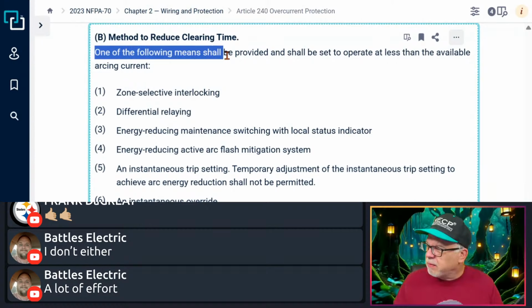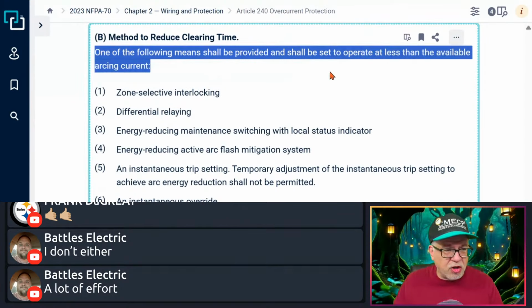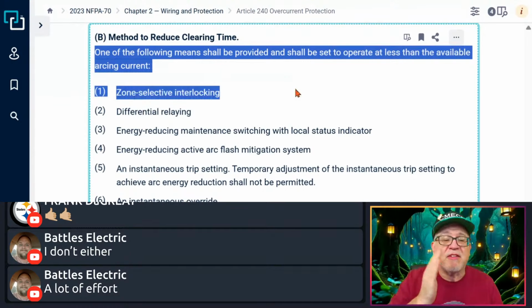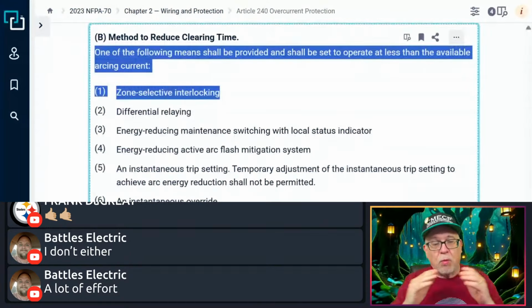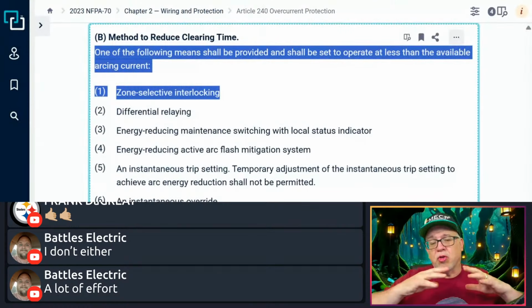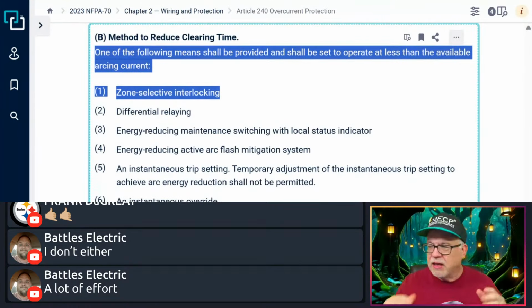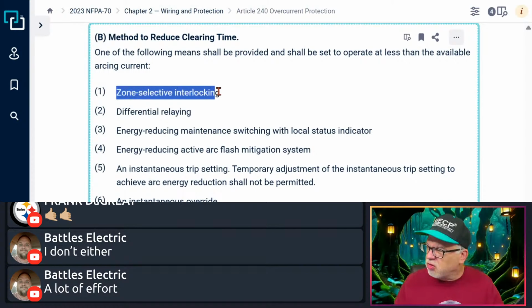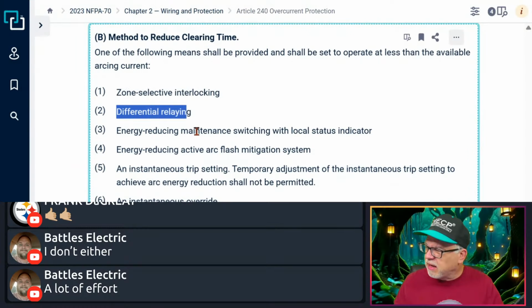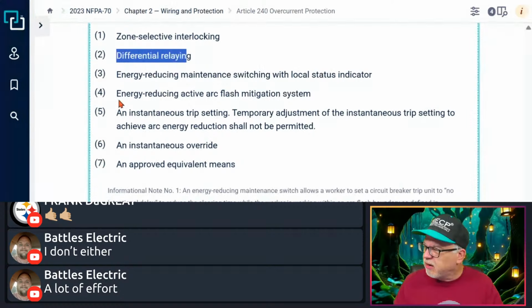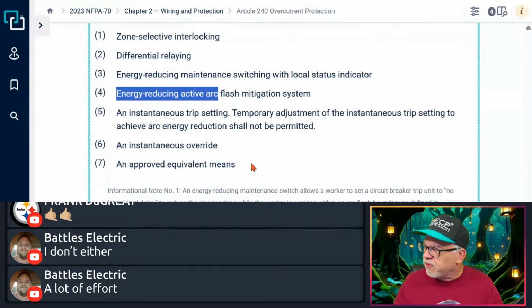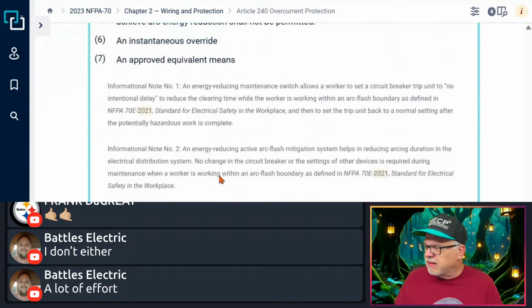And one of the following means shall be permitted and shall be set to operate at less than the available fault current. So you're going to be manually setting these to be set at less than the available fault current. And why are we doing this? Because this is also going to reduce the amount of arc energy. You can have all kinds of zone selective interlocking. Now, one we were talking about down here is energy-reducing active arc flash mitigation systems, which can be supplied by a manufacturer. Okay, that type of scenario.